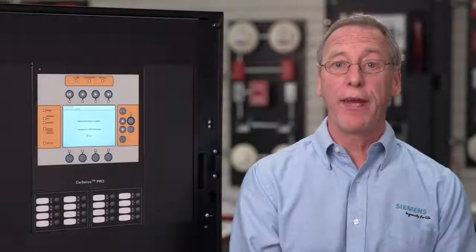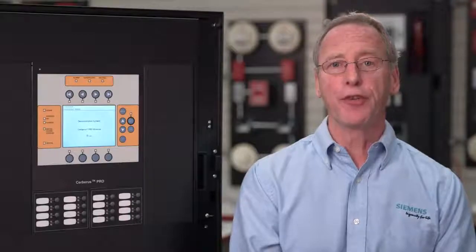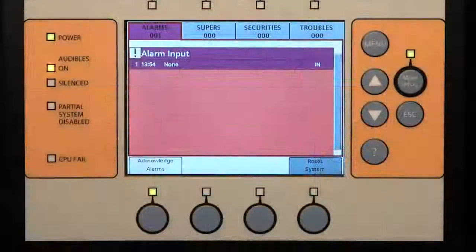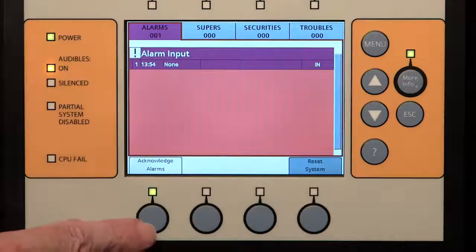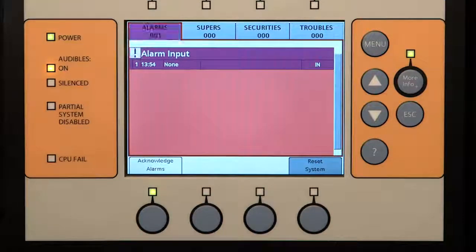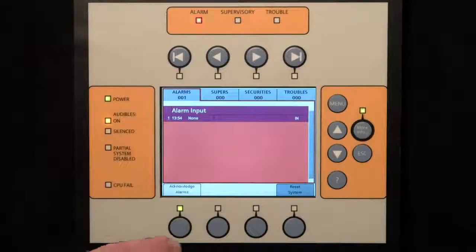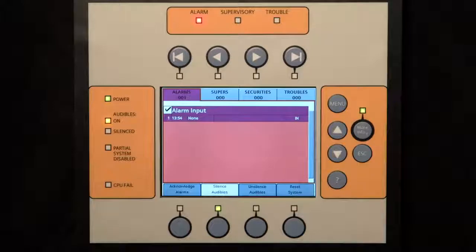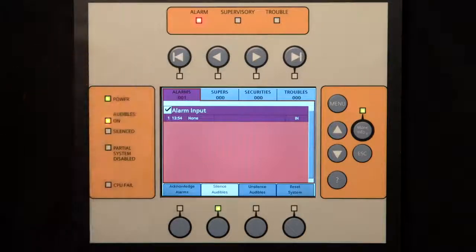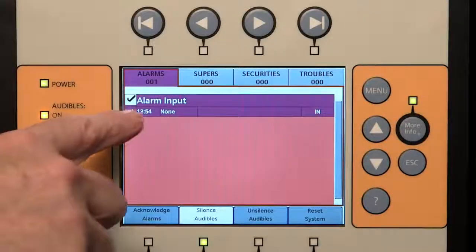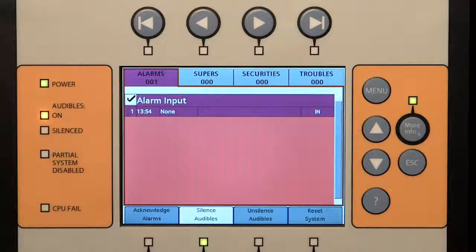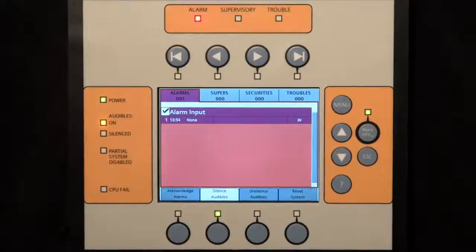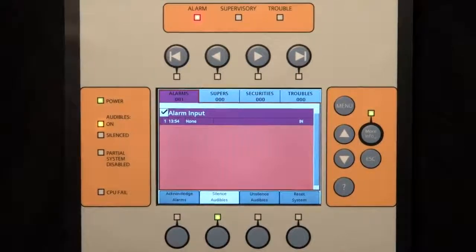Now I will create an alarm event and walk through the steps to operate and control this event. Just above the lower left button, the display will show that the button becomes an acknowledge button. The LED associated with this button is lit, showing that the button is now active. Pressing this button will acknowledge this event. It will also turn off the internal panel buzzer. The alarm LED will change from flashing to steady and the event displaying the exclamation point changes to the check mark to the left of the description.